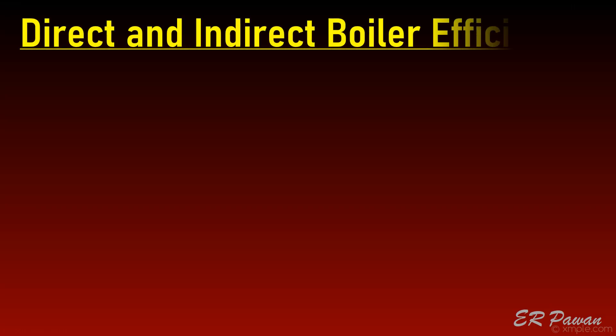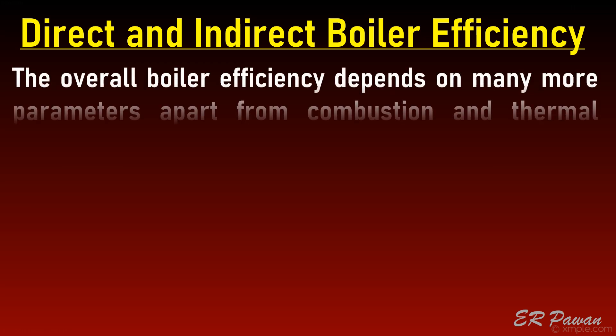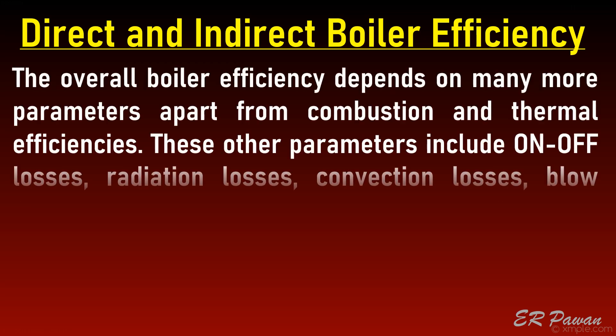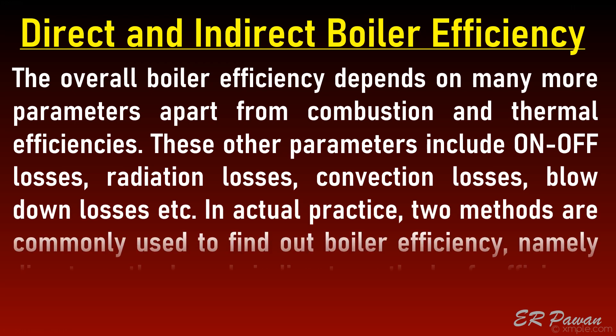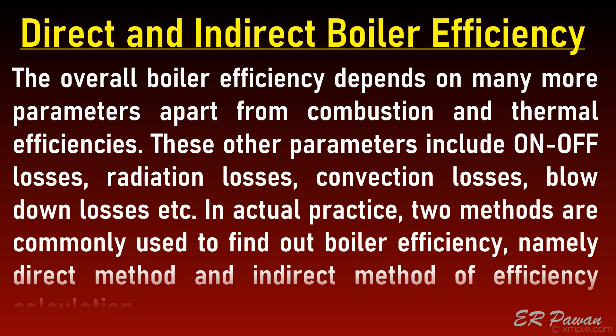Direct and indirect boiler efficiency: The overall boiler efficiency depends on many more parameters apart from combustion and thermal efficiencies. These other parameters include on-off losses, radiation losses, convection losses, blowdown losses, etc. In actual practice, two methods are commonly used to find out boiler efficiency, namely the direct method and the indirect method of efficiency calculation.